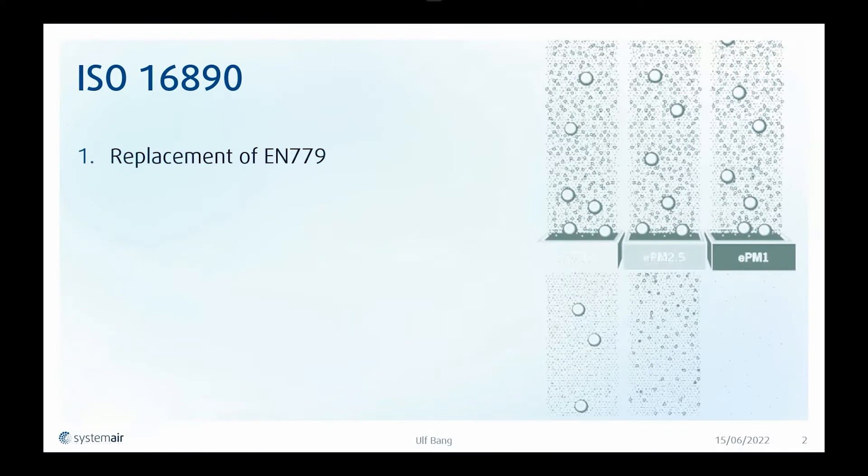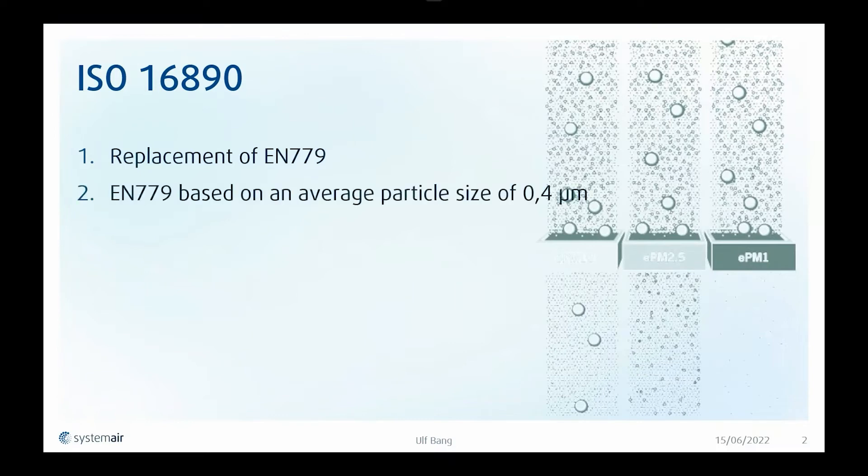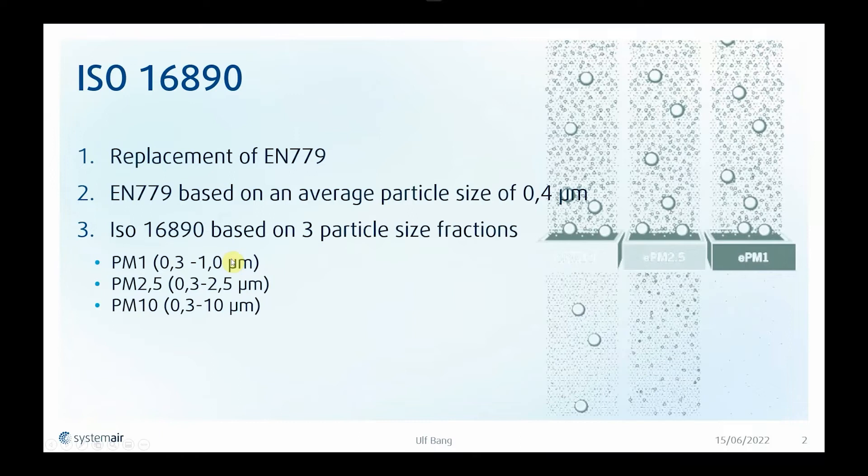ISO 16890 replaces the old EN 779. EN 779 was only based on an average particle size of 0.4 micrometers, and the new ISO 16890 is based on three particle size fractions: PM 1, PM 2.5, and PM 10.